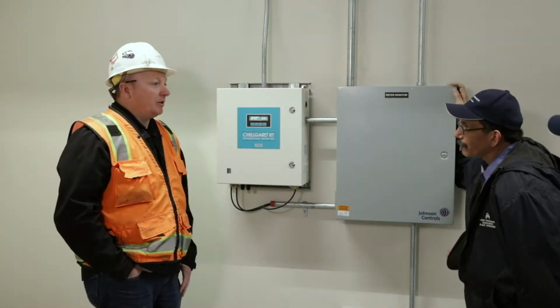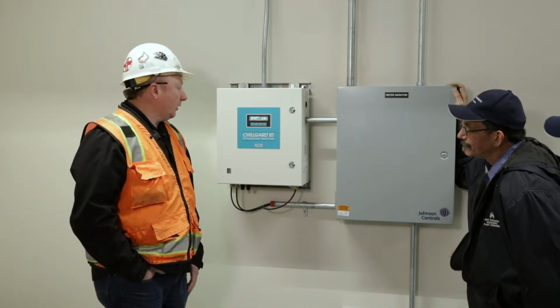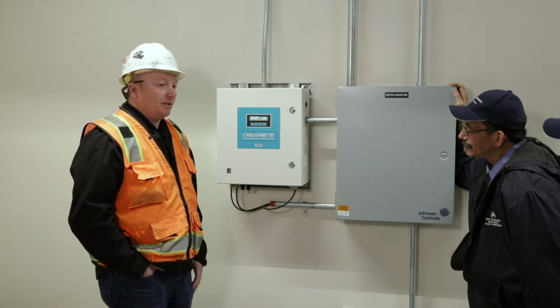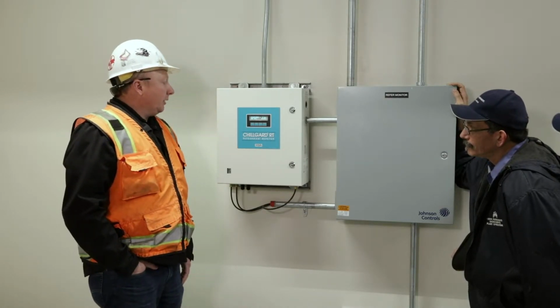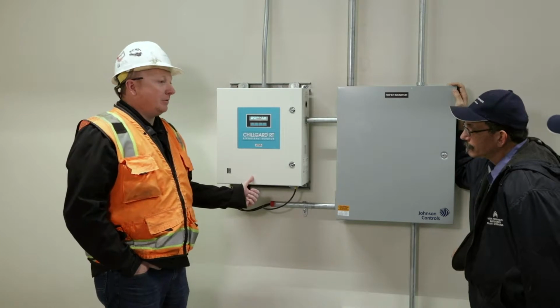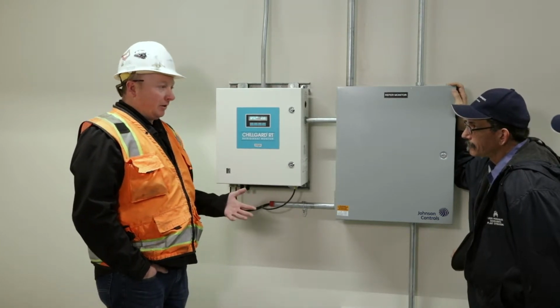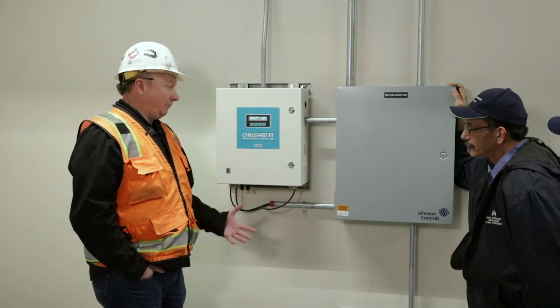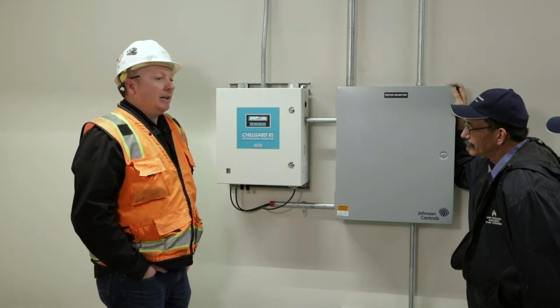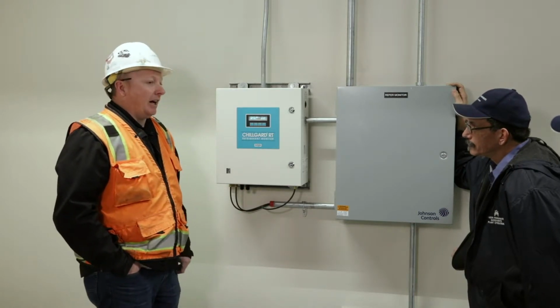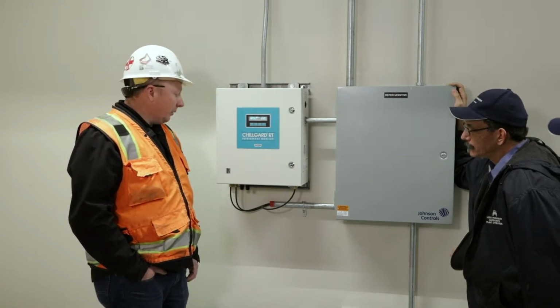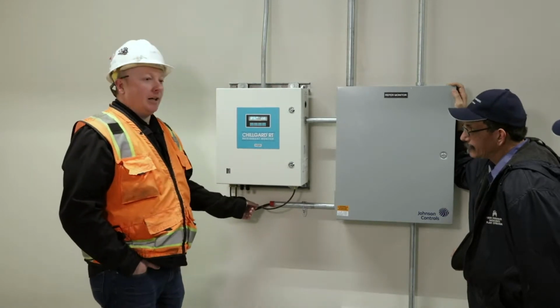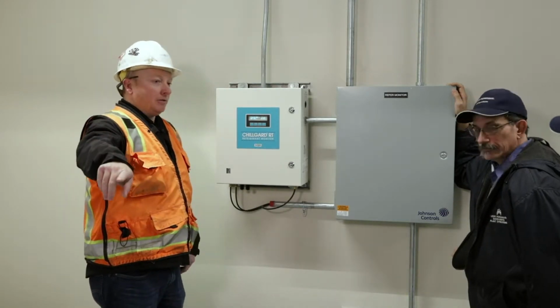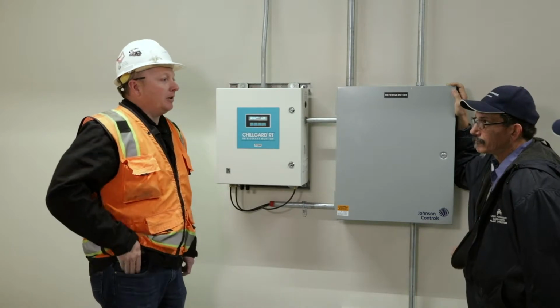Hi guys, my name's Martin Chance, and we're going to go over the leak detection system today. So we're using the Chillgard RT, which is the same one you guys have over at Morse Avenue, or similar, it might be the exact same one. It's basically an air pump style leak detection system. So we have poly tubing that runs under each chiller, and we have one sniffer under each chiller.